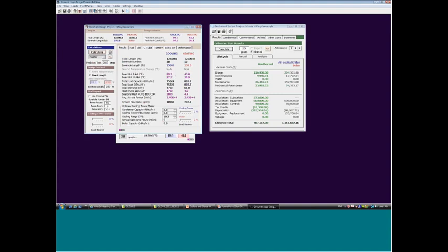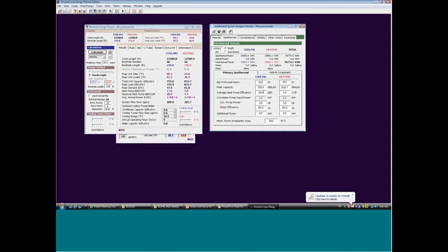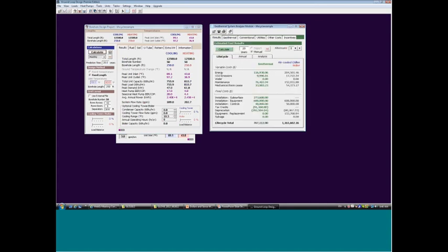My performance dropped. With my original design, my performance didn't change too much, actually. Interesting, it didn't change much at all for this particular design, but I've saved some drilling length in this example. So I'm going to import this design now and redo the calculations to see what would happen financially if I change the system a bit. The key variable here is, let's just look at these life cycle cost totals and see what happens to these numbers. Or we can look at the analysis.